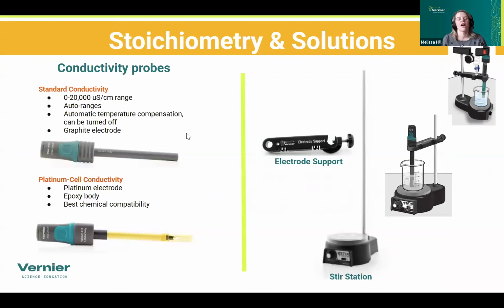We do offer two different types of conductivity probes. We have our standard conductivity probe here. And the range for it is 0 to 20,000 microsiemens per centimeter, and it does auto range. So there's not a switch on the box that tells you what range you will be measuring in. And it does, by default, have temperature compensation, the same 2% for sodium chloride, but that can be turned off. So you can actually look at conductivity readings as a function of temperature now, if you want to explore that aspect of conductivity, and it even has a live temperature readout. So you can turn on temperature, you can turn on conductivity, and you can turn on non-temperature compensated conductivity, all within the same sensor.